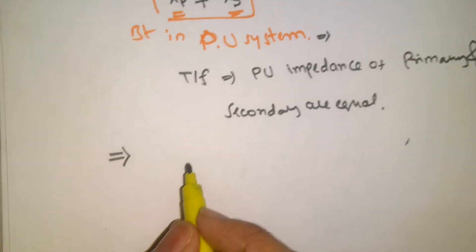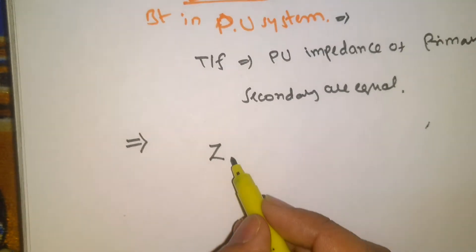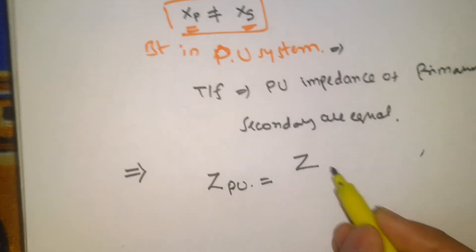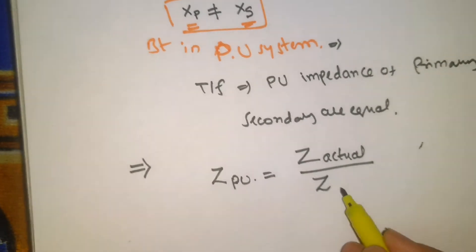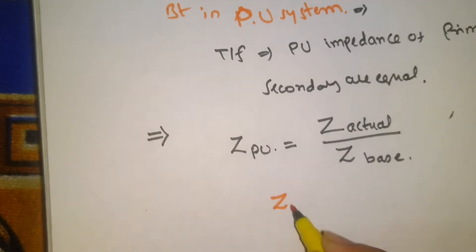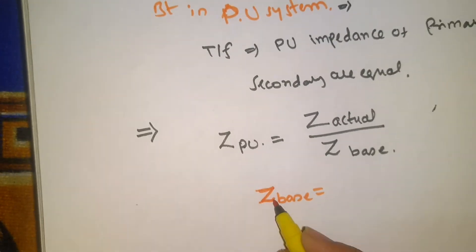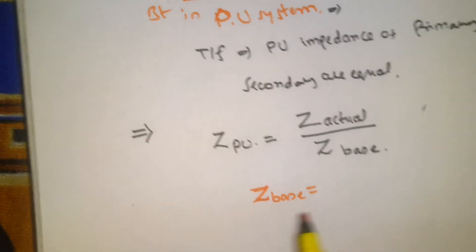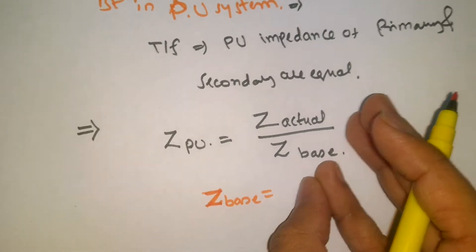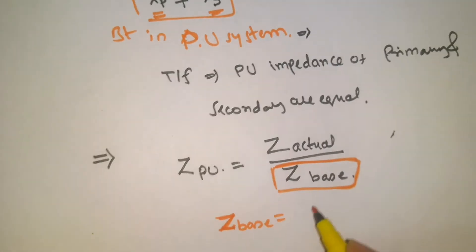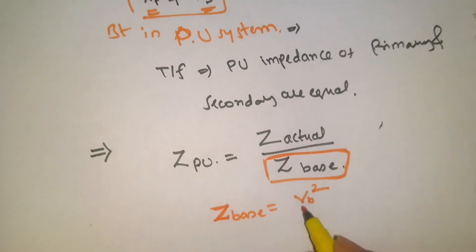Next, how to find impedance with new base values. I'm writing the very important formula for finding the per unit impedance. To get per unit impedance, we need the actual impedance value and the base impedance value. This formula is only for Z base impedance — not for base current, not for base voltage, not for base MVA. The formula is: Z base equals V base squared divided by MVA.